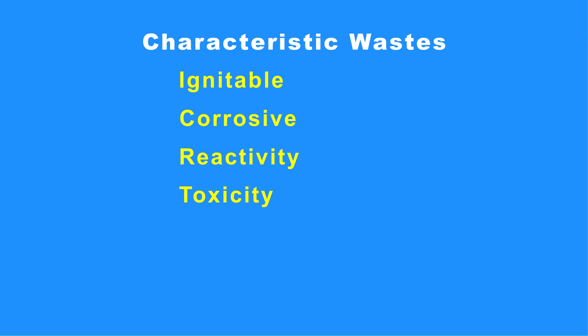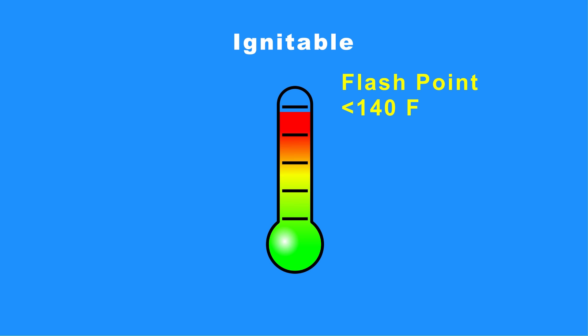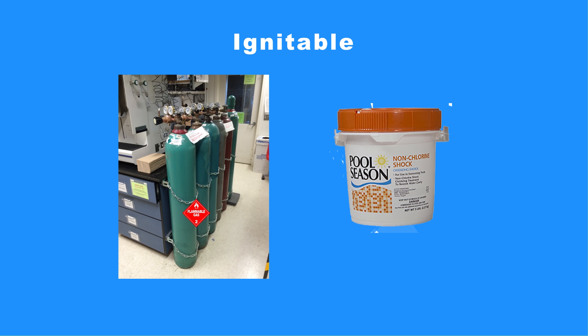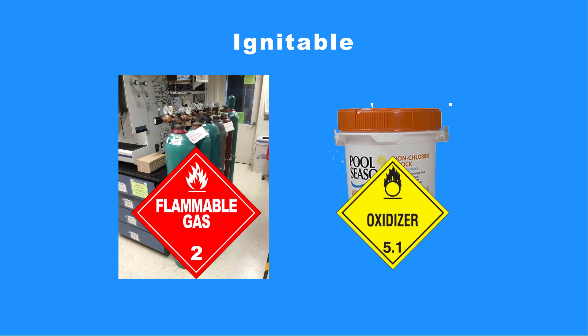Ignitable: Wastes that are hazardous due to the ignitability characteristic include liquids with a flashpoint below 140 degrees Fahrenheit, non-liquids that cause fire through specific conditions or are spontaneously combustible, ignitable compressed gases, and oxidizers.